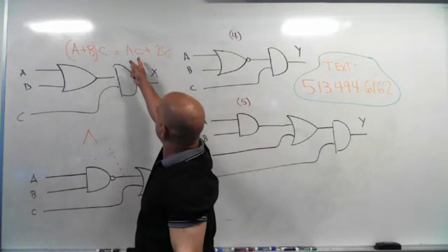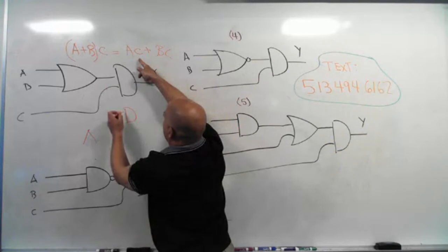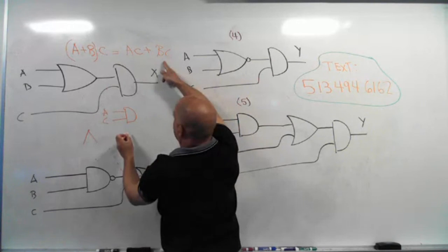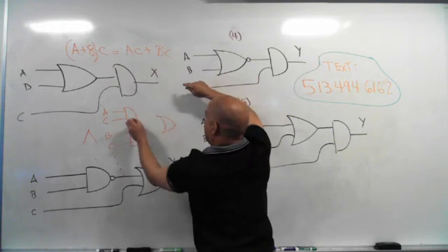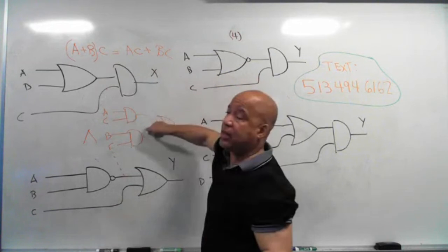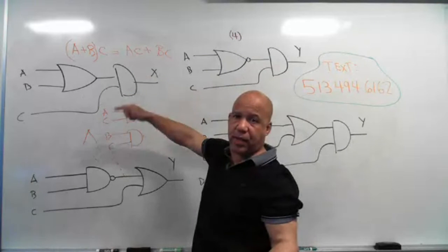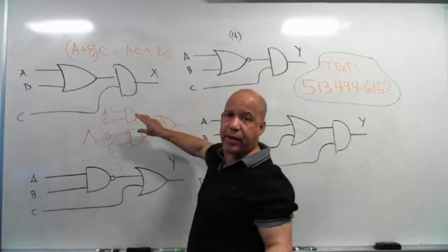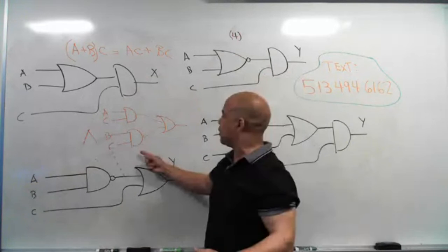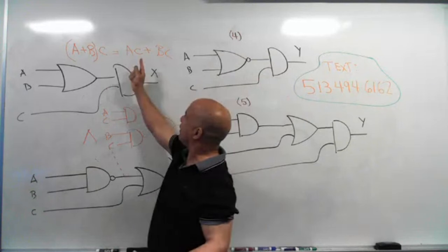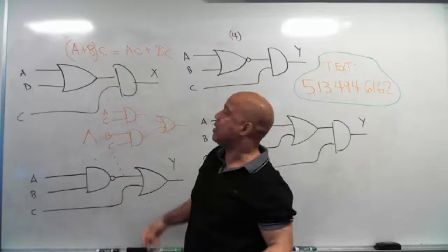Here you're taking this, we use 2 gates, but here to implement this, you need an AND and you need another AND, and then you'd have to take that and OR it together. So while both of these are logically equivalent, in the processor, you can take either one of these and put that in the processor for a PLC and run it. And honestly, if this was the only circuit you had in there, it wouldn't matter. But you can imagine if you had a lot of lines of code, then you want the processor to run as fast as possible. So even though the left side and the right side of this are logically equivalent, in theory, this will run a little bit faster because there are fewer gates. But yeah, you can use either one.